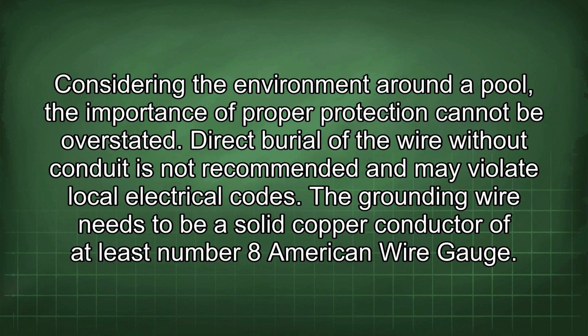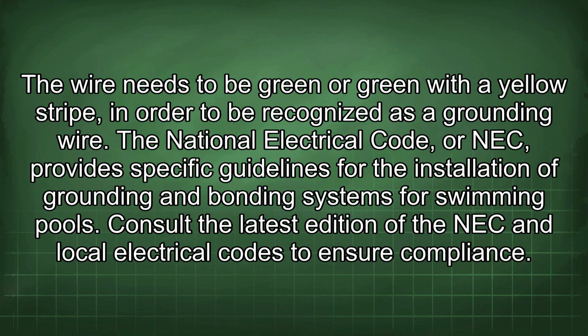The grounding wire needs to be a solid copper conductor of at least number 8 American wire gauge. The wire needs to be green or green with a yellow stripe in order to be recognized as a grounding wire. The National Electrical Code, or NEC, provides specific guidelines for the installation of grounding and bonding systems for swimming pools. Consult the latest edition of the NEC and local electrical codes to ensure compliance.